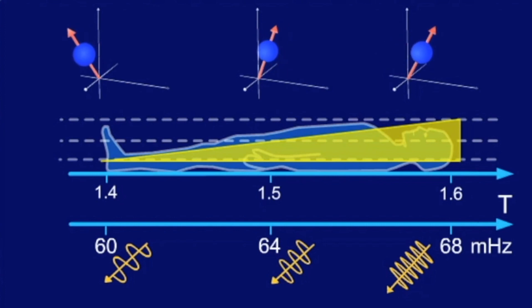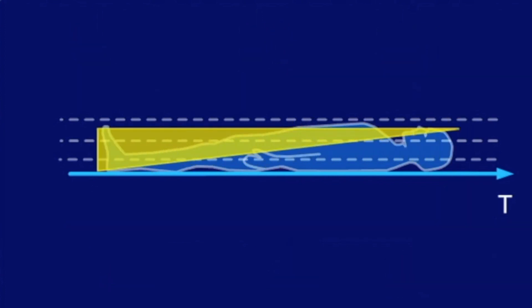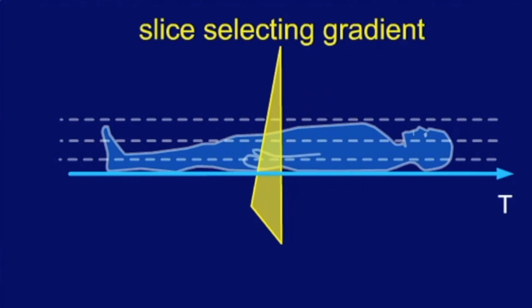As gradient fields can be superimposed in any direction, it's possible to define not only transversal slices, but all kinds of different imaging planes without moving the patient. The gradient field that enables us to examine a specific slice is also called slice-selecting gradient.